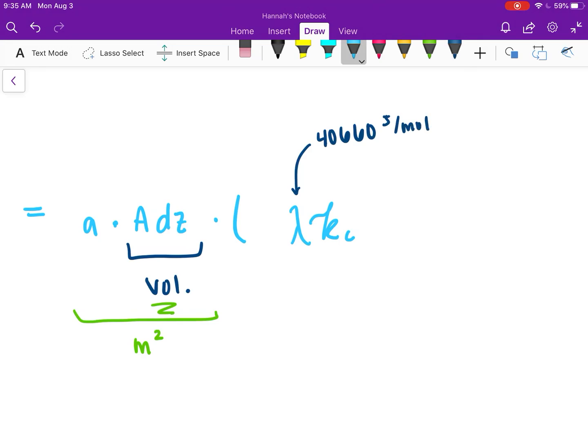And then this is really important, is this negative sign here, and that negative sign is negative because the temperature of the water decreases as it goes down the cooling tower, so we need to have that negative in there so we have the correct sign for this part of the equation.